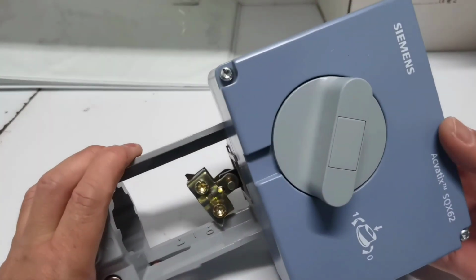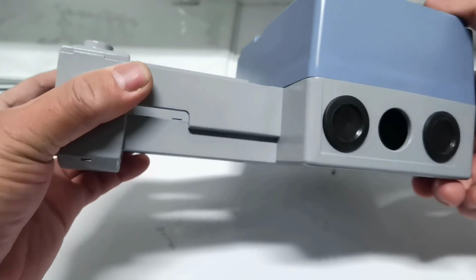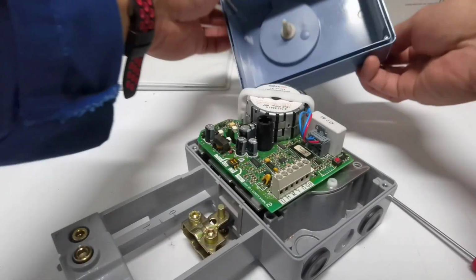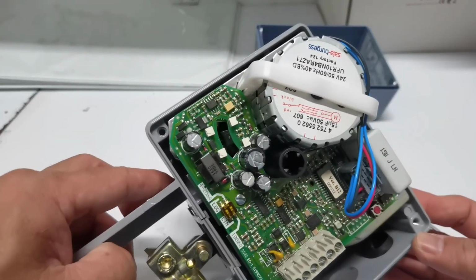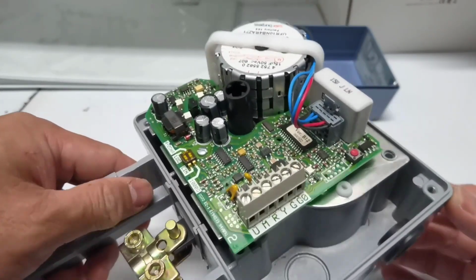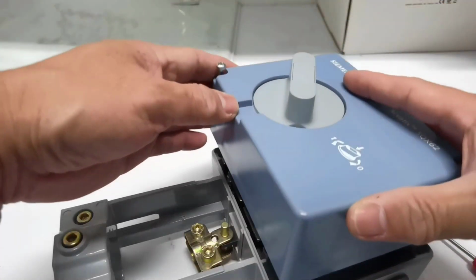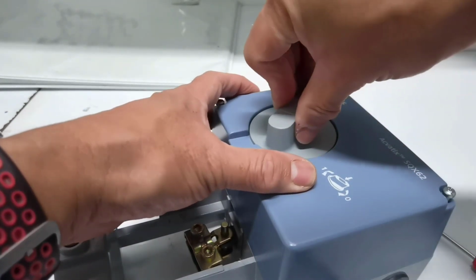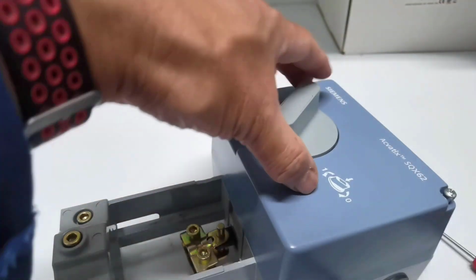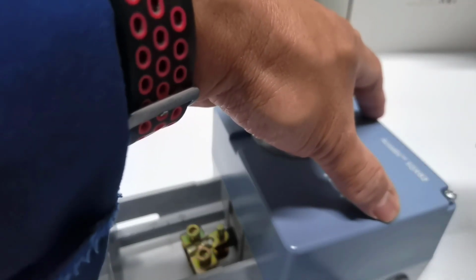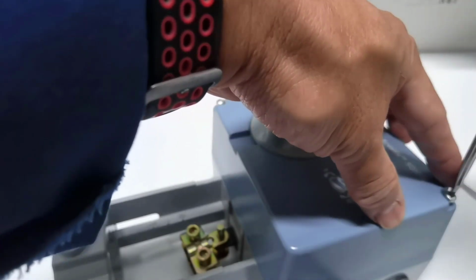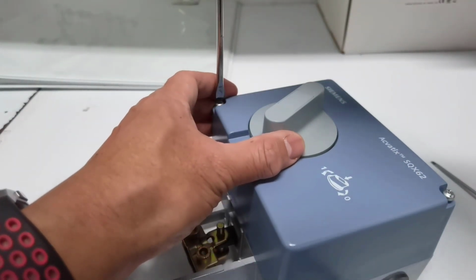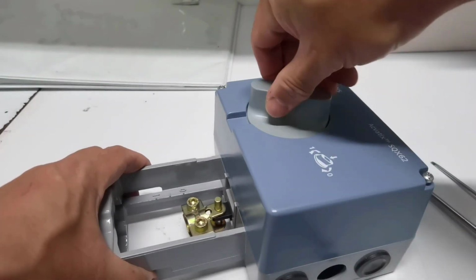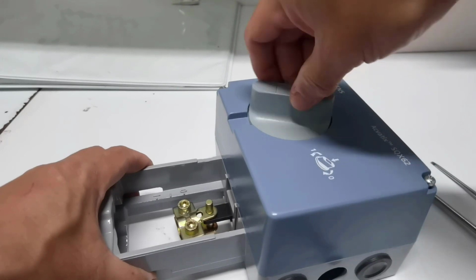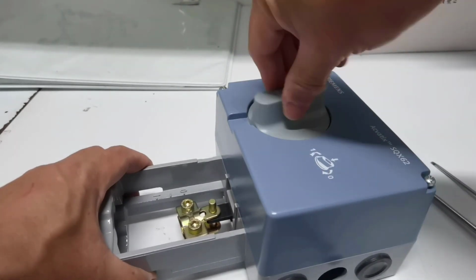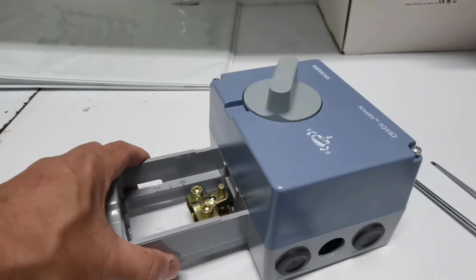The SQX62 actuator has a 24 volts AC operating voltage and has 3 positioning signals: 0 to 10 volts, 4 to 20 milliamp, and 0 to 1000 ohms. The recorded positioning signals control the synchronous motor by means of microprocessor electronics. This motor generates the desired stroke via a blocking-proof gear train and gear rack. The motor has a protective function that effectively prevents a thermal overload of the synchronous motors in swinging control circuits or highly dynamic control.